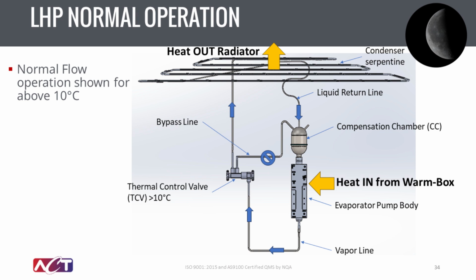So what does that look like in the whole system? The thermal control valve, we can see here on the left-hand side of the diagram. So this is showing the loop heat pipe with the thermal control valve and the radiator on top. So heat is coming in from the warm box into the evaporator pump body. The two-phase working fluid is then boiling off, and the vapor is leaving out the bottom and going to the thermal control valve. During normal operation, the vapor then goes up to the condenser serpentine, where the heat is rejected out of the radiator, and the two-phase condenses into liquid, which then returns in through the top, through the compensation chamber and back into the evaporator pump body to then be able to pick up more heat.